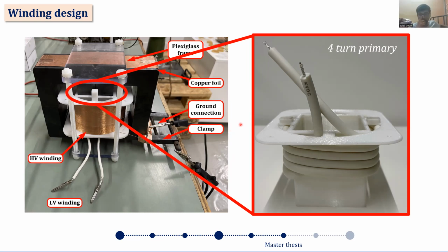In my design, in the high voltage winding, we added a lot of heat shrink tubes, and again resin cast that end ring portion, and added a metal shield for field uniformity.